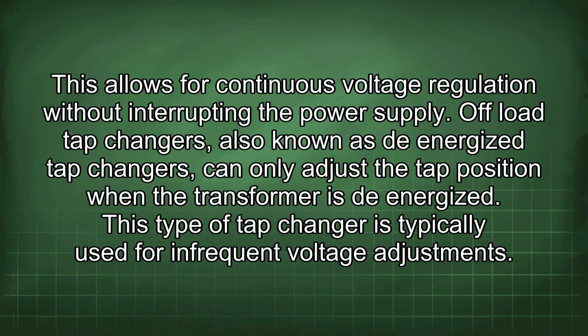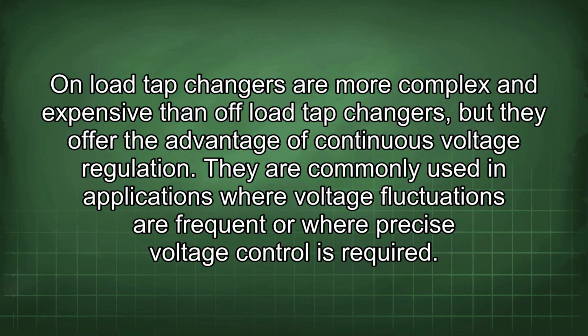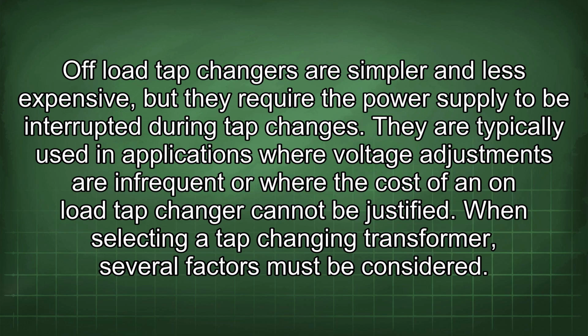Off-load tap changers, also known as de-energized tap changers, can only adjust the tap position when the transformer is de-energized. This type of tap changer is typically used for infrequent voltage adjustments. On-load tap changers are more complex and expensive than off-load tap changers, but they offer the advantage of continuous voltage regulation. They are commonly used in applications where voltage fluctuations are frequent or where precise voltage control is required. Off-load tap changers are simpler and less expensive, but they require the power supply to be interrupted during tap changes. They are typically used in applications where voltage adjustments are infrequent or where the cost of an on-load tap changer cannot be justified.